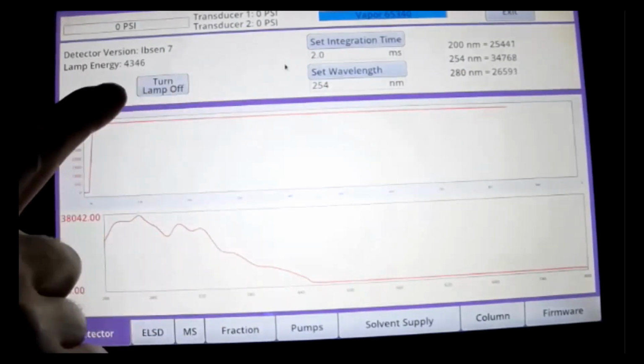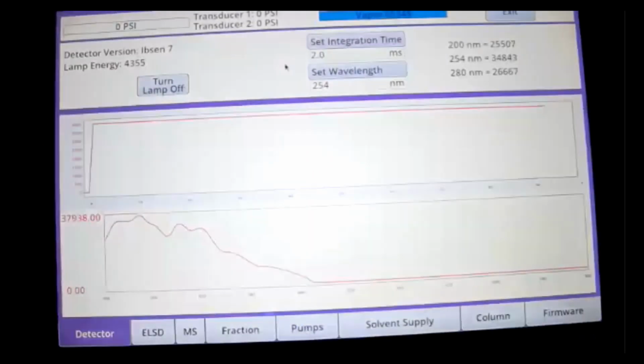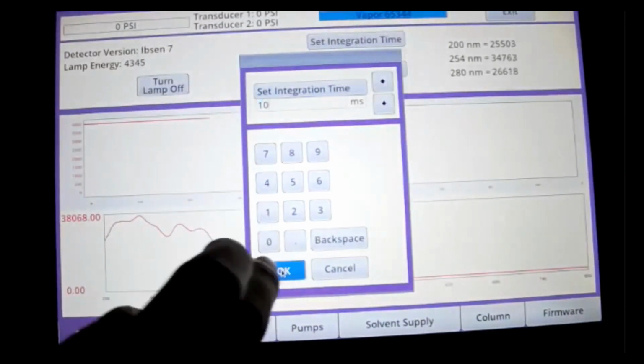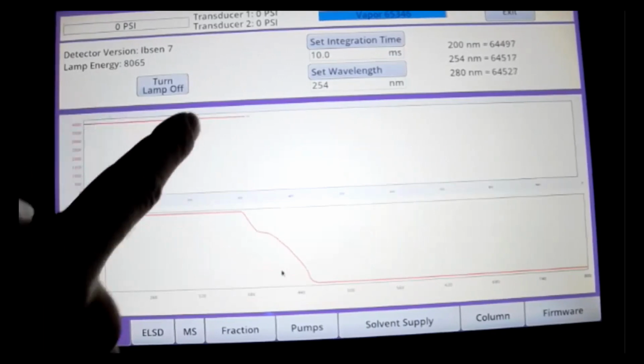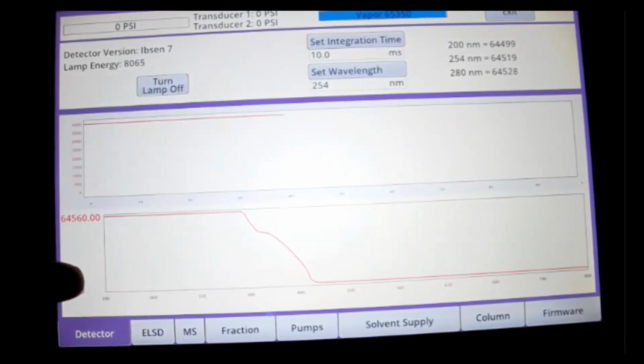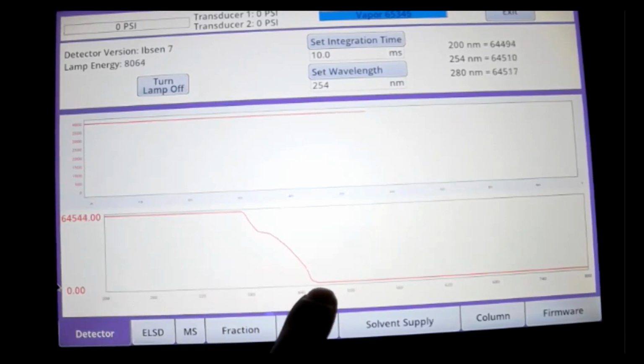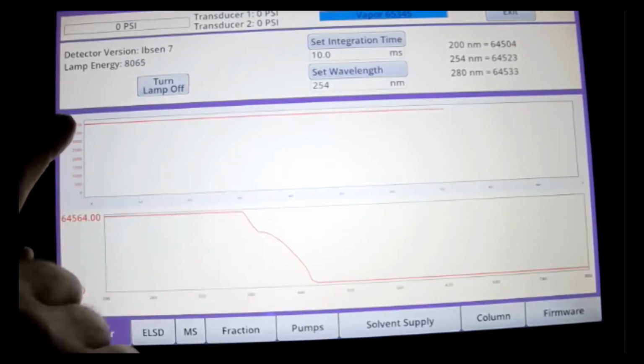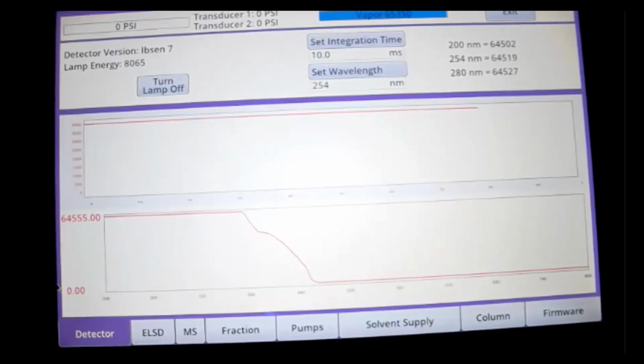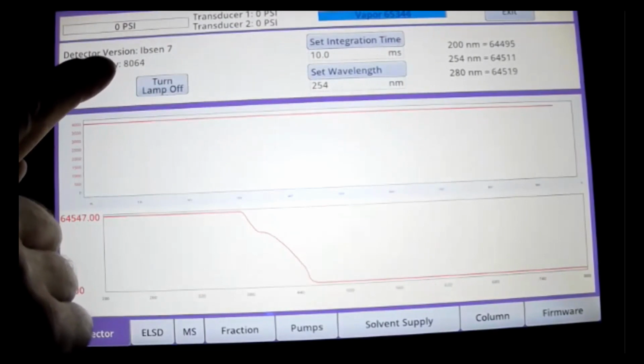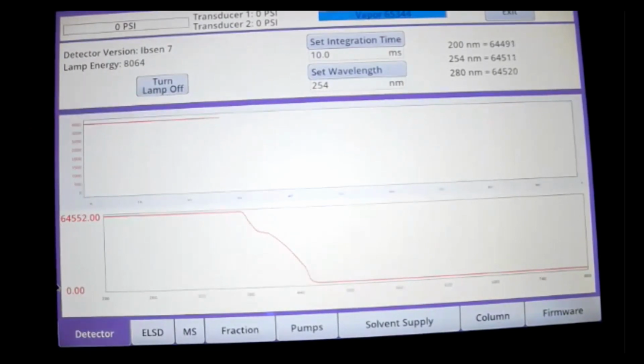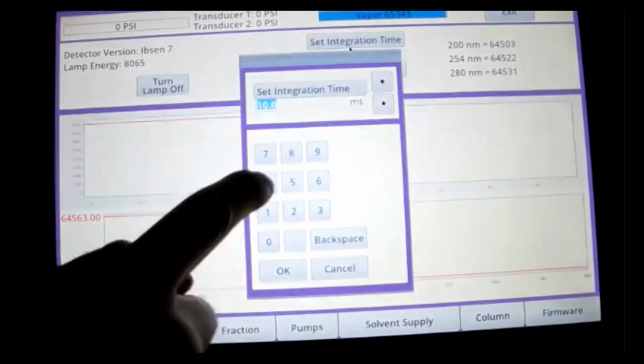Now, if your integration time is set to 2 and you're over 4,000, you're good. Holy cow, is that good. Well, let's mess with it, see what happens. Let's change this to 10. And it's still as high as it possibly can be. Down here is an absorbance meter showing you what spectrum is being detected right now, and it cuts off here at about 460-ish, but everything else is pegged. Your light energy at the top is completely maxed out. You couldn't ask for better light energy. If I set this to 10, I'd like to see above 6,000. That makes me nice and happy, but I don't have a spec to give you other than you just want to make sure on these two that you're getting good detections on your graph. So we'll set this to the 40 like it talked about earlier.